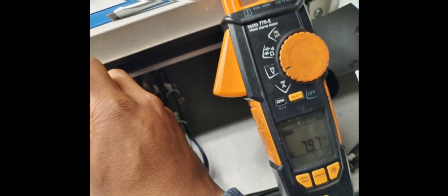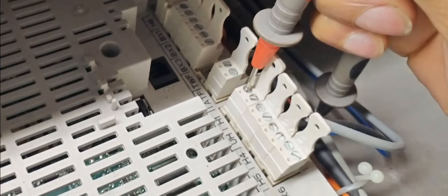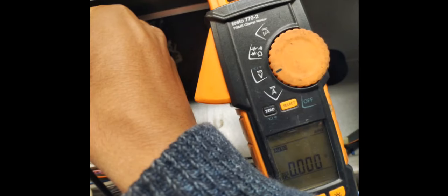So I was just making sure there was a switch live to these particular Potterton commercial boilers. This is where I checked on this Potterton commercial boiler on H1. I was getting about 8 volts DC. Here's another boiler where the switch live wasn't receiving any power from the boiler. And you can see there's no current.